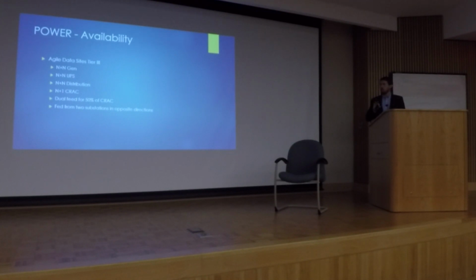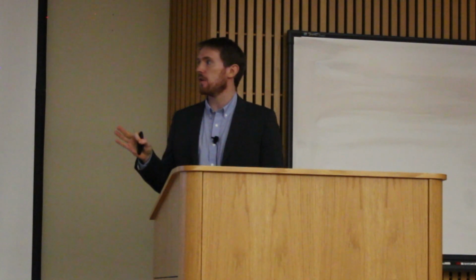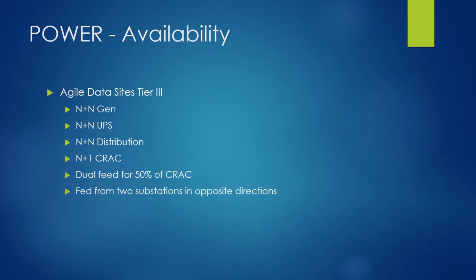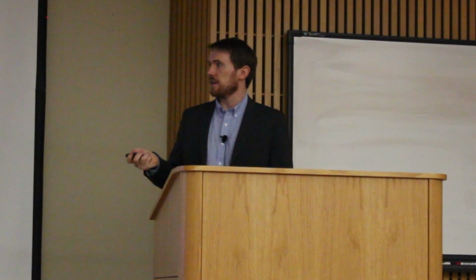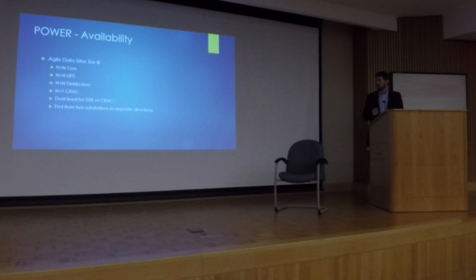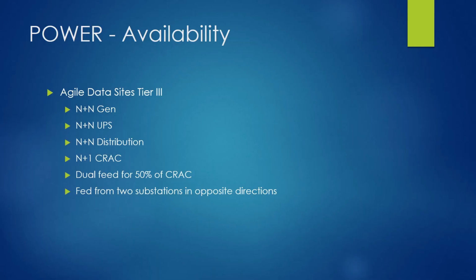Agile data sites at the moment can provide tier 3 level or above electrical distribution. That includes 2 redundant generators, N plus N. If any one of those generators were to fail, the others would take it up without any interruption. N plus N UPS is the same thing - if any one UPS unit were to go down, no disruption. N plus N distribution means the entire side of the electrical distribution could be shut down and we would still have all of the cooling power that we need.